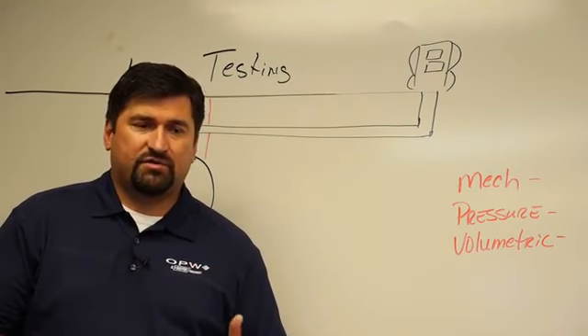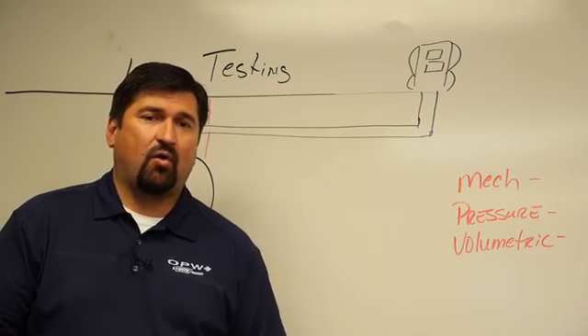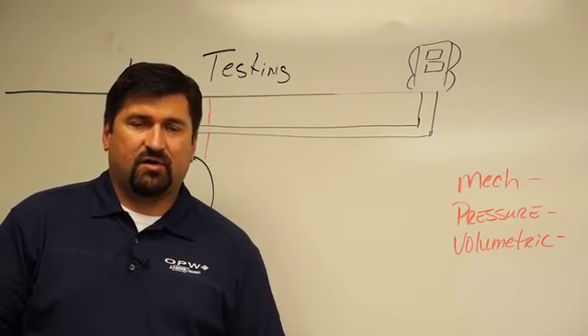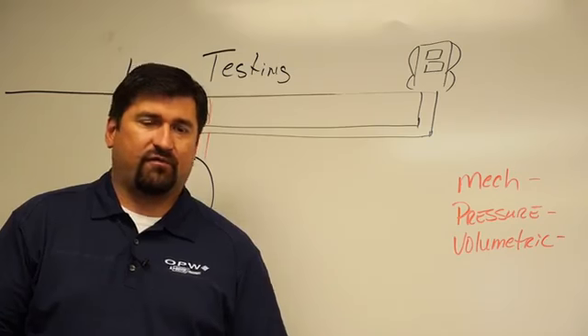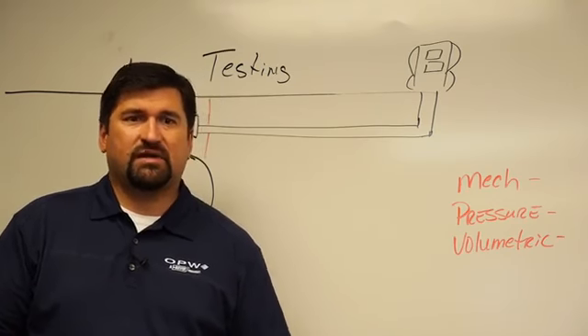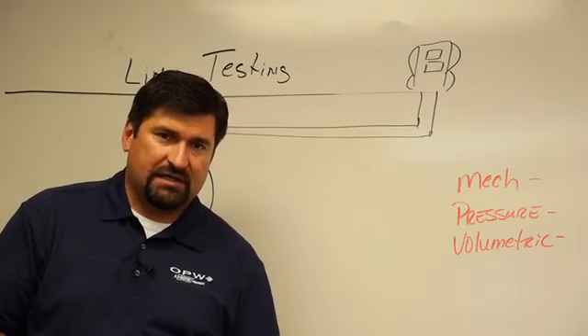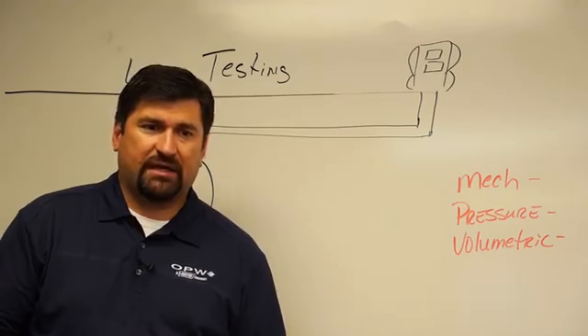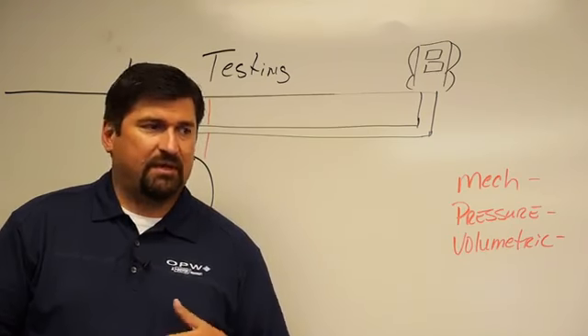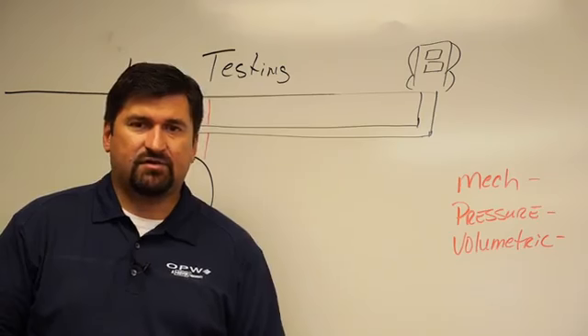Well, at the point in which you restrict flow, and this will normally happen in cold weather, anybody that's from the north will know that on a cold night, when they go to fill up the first thing the next morning and squeeze the nozzle, it just trickles out. You release the nozzle, let the line pressure up again, it'll reseat the poppet and the mechanical resets, and they're able to start flowing.